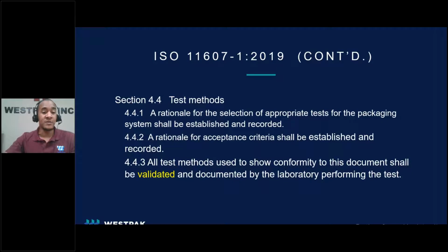So for Section 4.4, it calls out the requirement for test method validation. This section details some of the parameters and justifications required by TMV. This section states that a rationale or justification must be made and documented while selecting test methods. It also calls out the requirement to establish and provide reasoning for determining the acceptance criteria of these test methods. Lastly, you'll notice our favorite word, validated, being used once again.